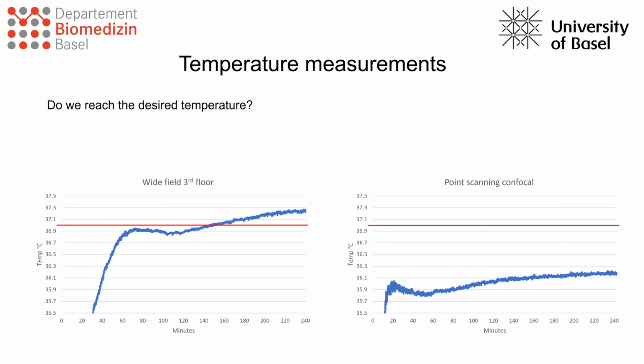We then wanted to know, of course, if the desired temperature is actually reached. And here we found that in some cases we actually get slightly higher temperatures. Instead of 37, it's around 0.3 higher. And then in other cases, we did not even reach the 37 degrees. So we were quite far away, almost a degree away from the set point. And then, of course, we could use this information to slightly adapt our set points so that we then finally reach the 37 degrees.